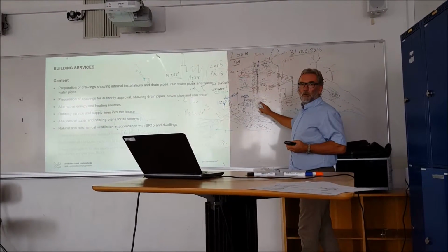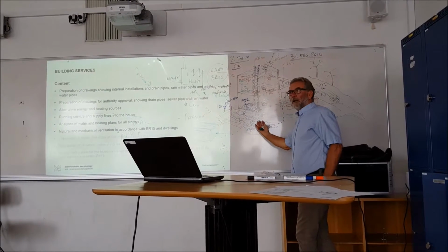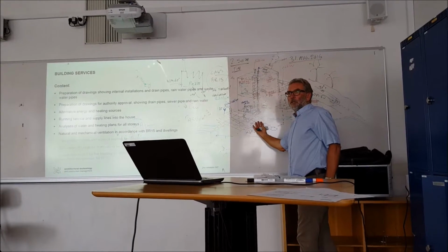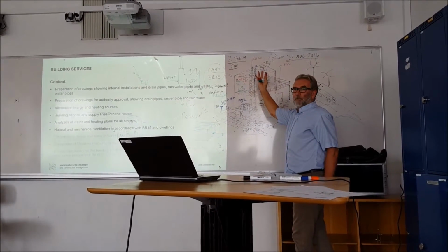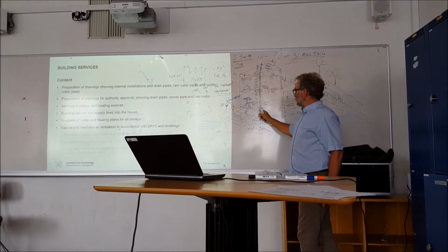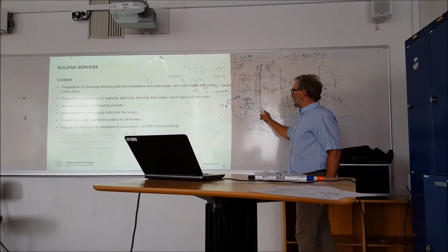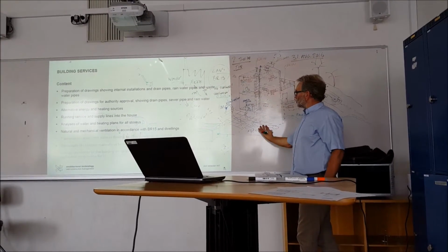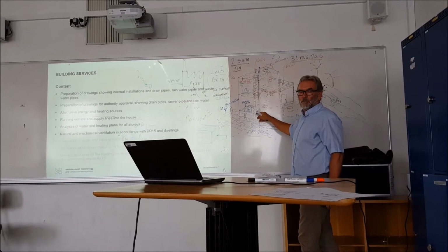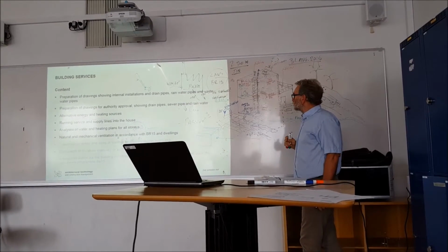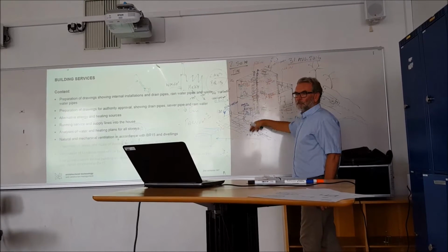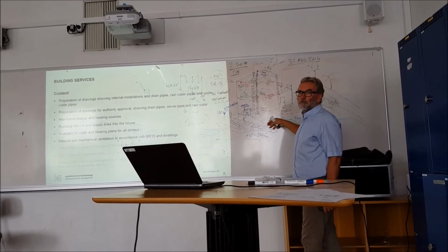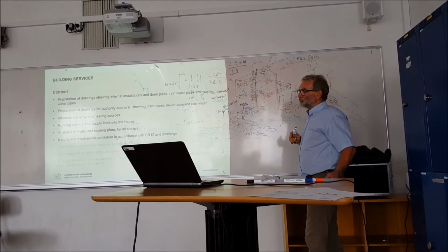And that will bring me to, remember, later on I'll give you a presentation about the fire. What do we do with the fire? Because you know in the fire regs you've got to isolate the fire from the basement, from the rest of the building. And what I suggest is that you make a fire sealing here, and you seal all the pipes where they go through the fire stop here. You make a fire stop at that point, so you seal the basement from the rest of the building. So you're isolating the shaft from the basement, the same way as you isolate the stairwell from the basement to the rest of the building in fire.